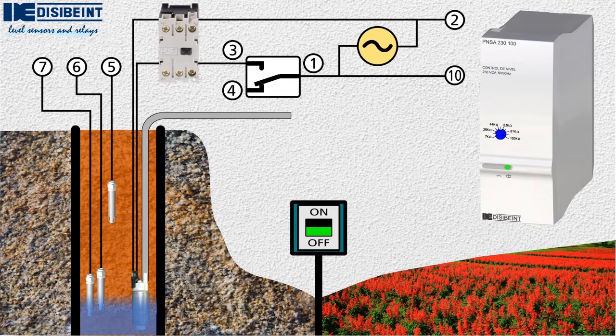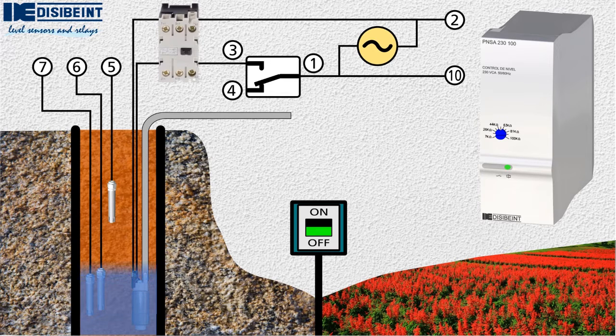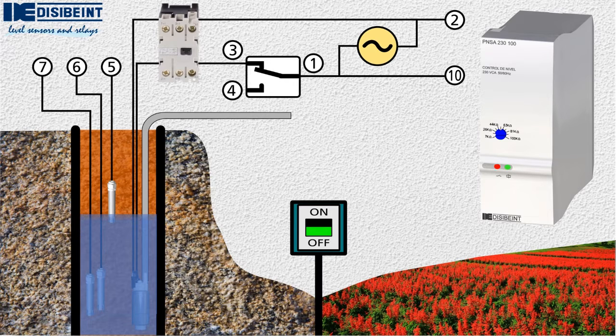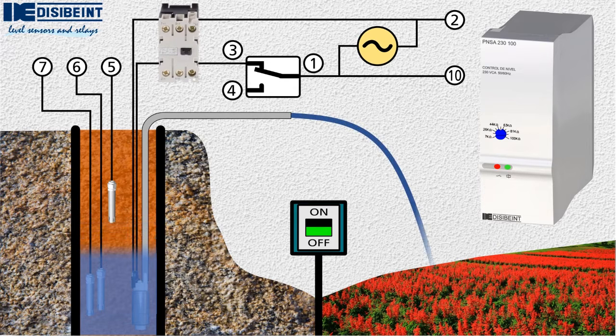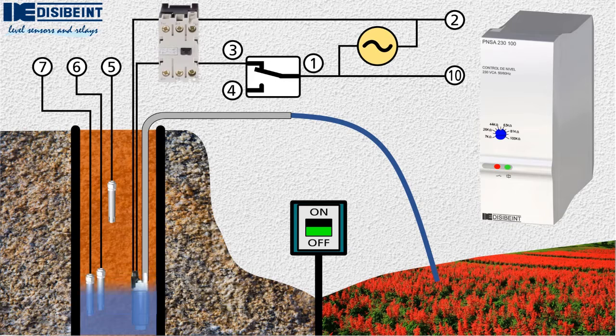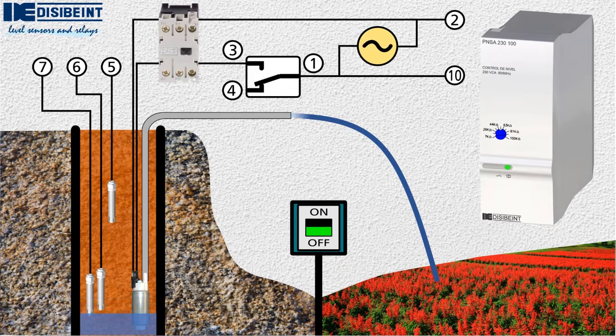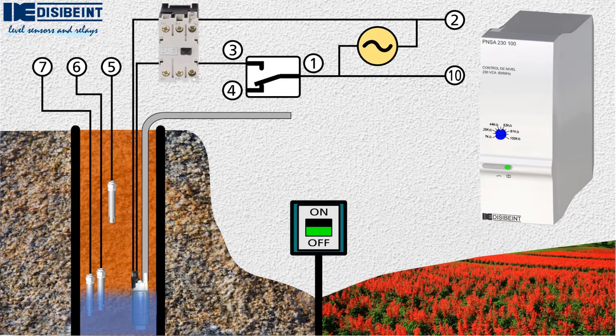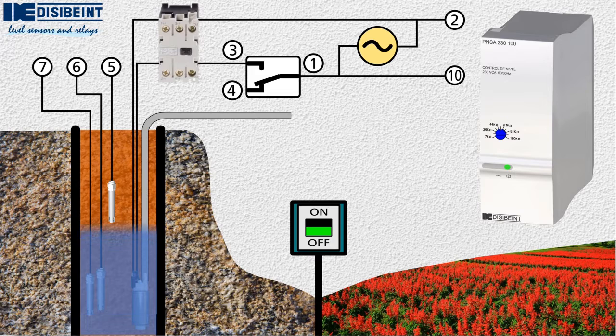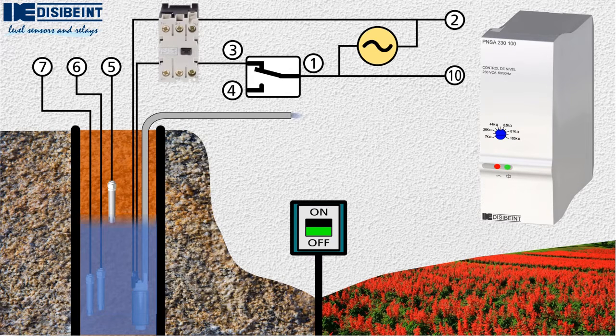If the power supply to the system is not cut off, the irrigation will restart when the water level reaches the maximum probe, repeating this cycle uninterruptedly until we act on the general switch. This will happen whenever the flow ejected by the pump is greater than the flow with which the well is naturally filled.